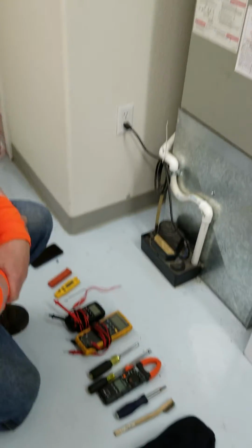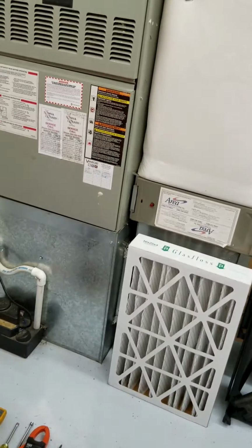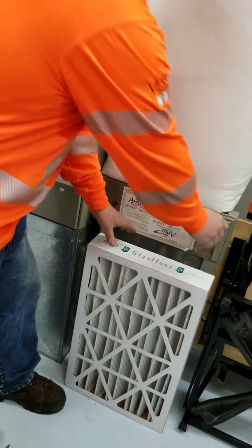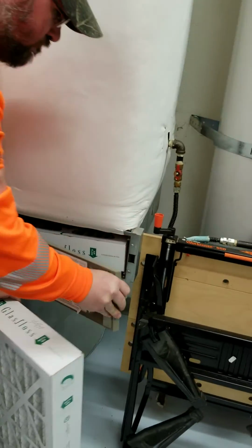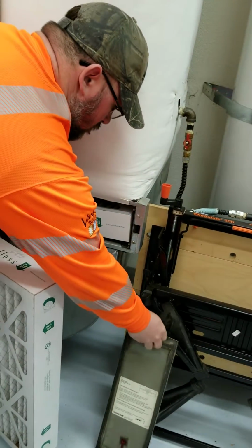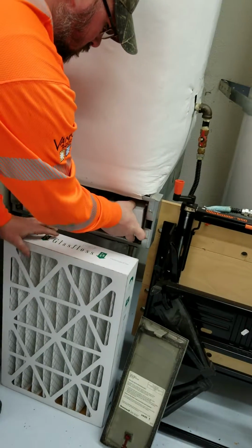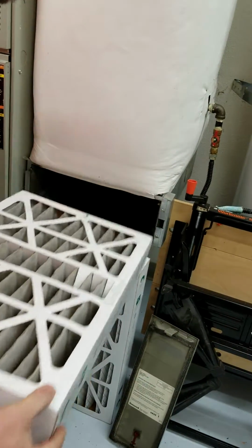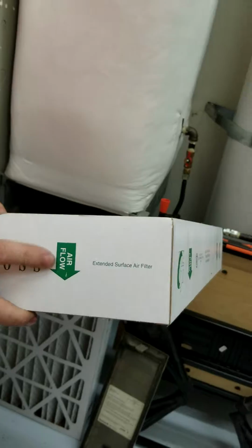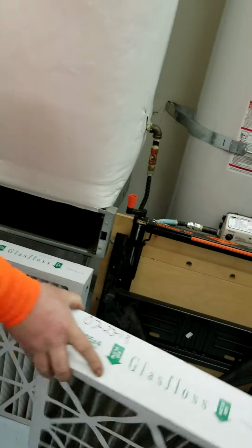So if you want to go ahead and begin, Damien, first thing we're going to do is replace the furnace filter. And this one goes inside the cabinet right there. Something to note: there's an airflow arrow. The airflow arrow always points toward the furnace.